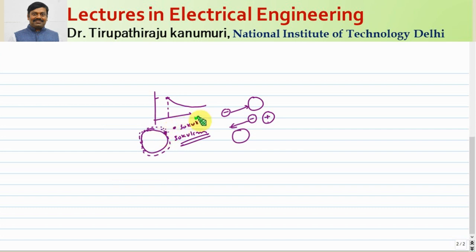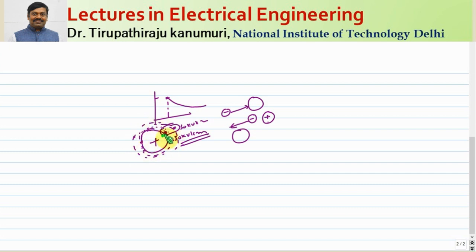At the point where the field equals 30 kV per centimeter, the region between the conductor surface and that point gets ionized and starts acting as a conductor. The ionized particles accumulate on the surface of the conductor and contribute to conduction, becoming visible in the form of light. The color of this light depends on the polarity of the conductor — for the positive conductor, electrons form and the color will be different from that of the negative conductor.